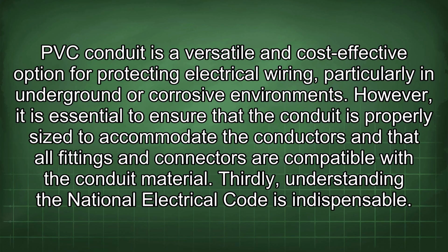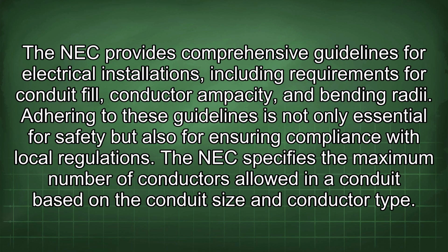Thirdly, understanding the National Electrical Code is indispensable. The NEC provides comprehensive guidelines for electrical installations, including requirements for conduit fill, conductor ampacity, and bending radii. Adhering to these guidelines is not only essential for safety but also for ensuring compliance with local regulations. The NEC specifies the maximum number of conductors allowed in a conduit based on the conduit size and conductor type.